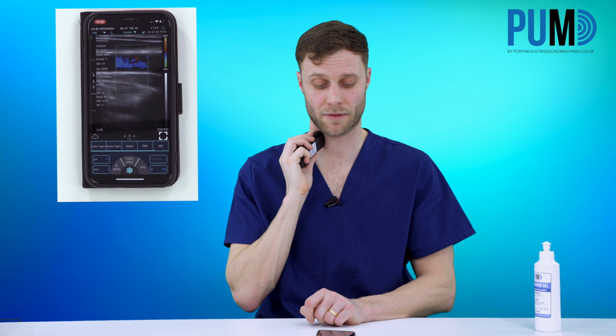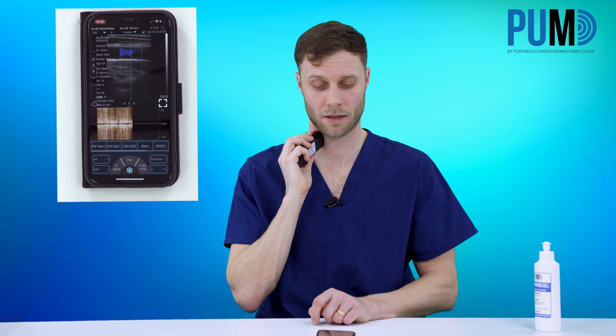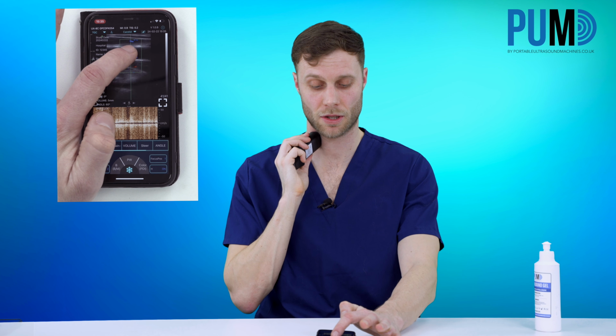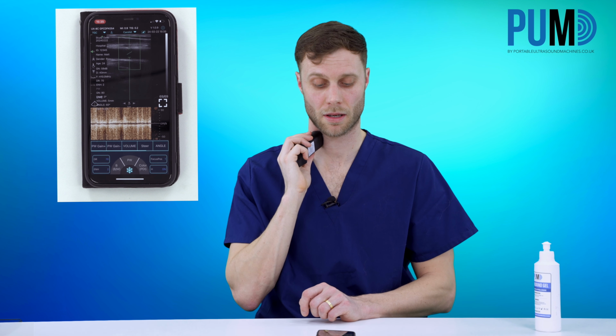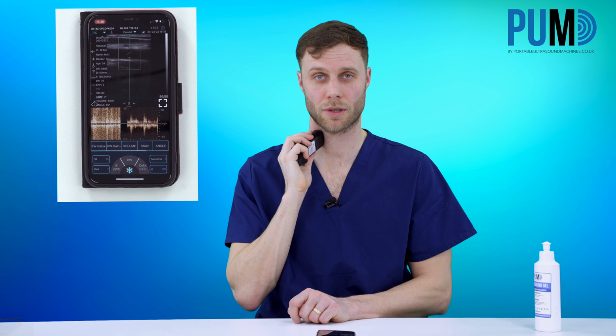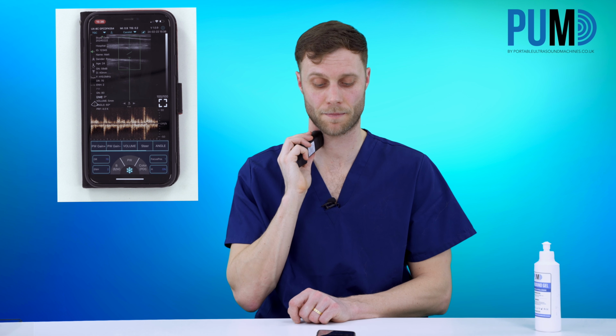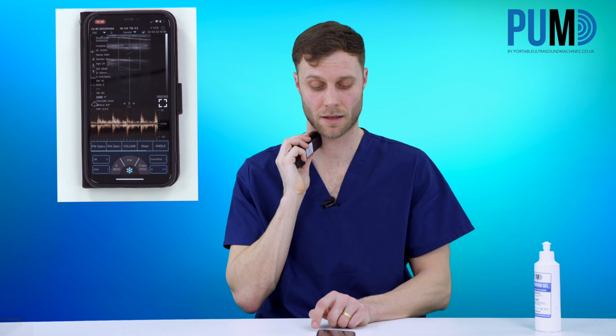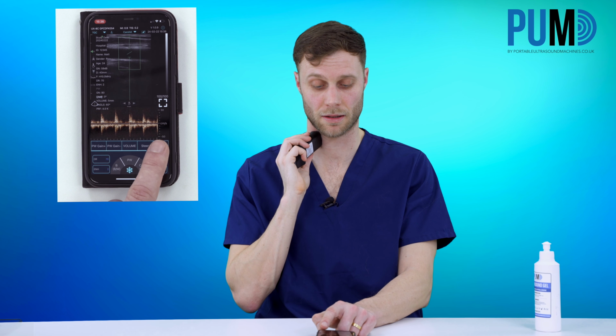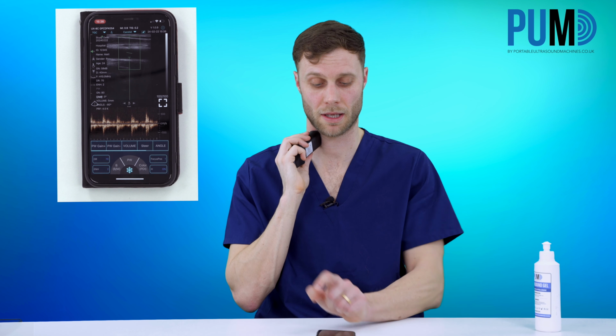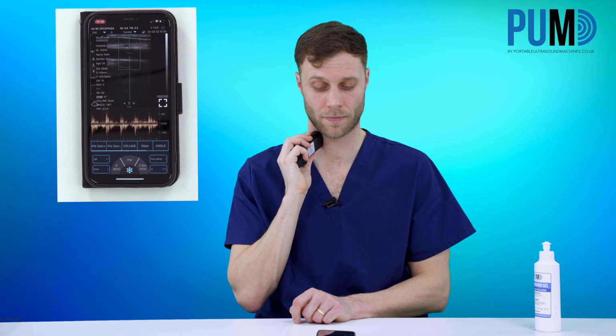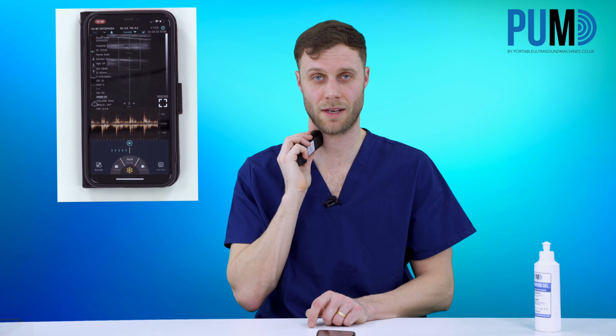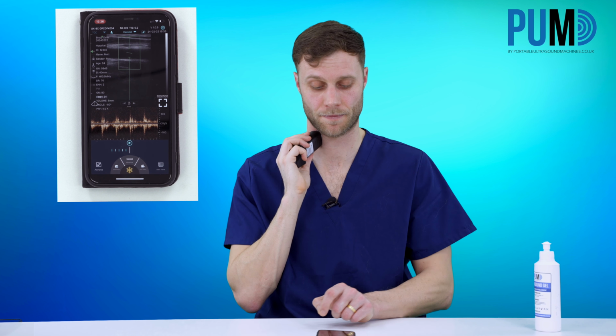To use my pulse wave, I hit the PW, and this will bring up my cursor. And I, once again, using the touch screen, can drag my cursor into position, and you will see a pulse wave for my carotid appear on the bottom there. And you do have the option of reducing the gains and also the steer and the angle. So for this, I may just want to make the angle slightly more horizontal, and we can freeze, save these images, and also take measurements.